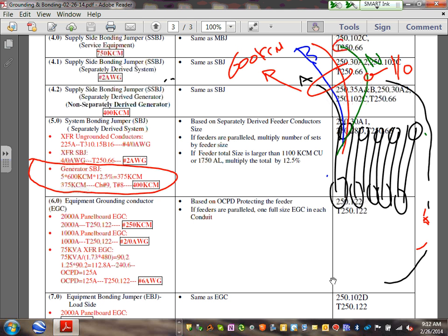Unless you want to sell one of your arms or legs to buy a 375 custom design cable, you have to go to the next standard. 375 kcm, chapter 9, table 8, gets you 400 kcm. So that wire that tied the neutral to the ground inside the generator, like inside the transformer, is called the system bonding jumper. In this case, it will be a 400 kcm big wire, or it could be a copper bar. Remember these copper bars, guys, that we did? Any comments, guys, about the system bonding jumper at the generator? So that's your system bonding jumper at the generator.